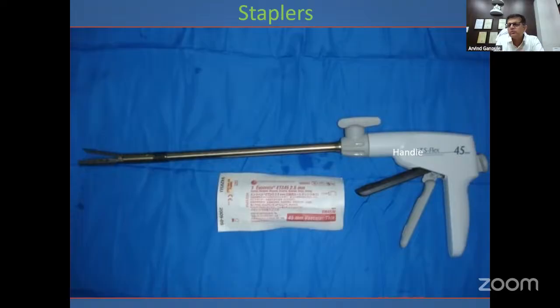So all those horrendous videos that you see, most of the time they are reusing the staplers, or they are not using the proper cartridge. As far as the staplers are concerned, you have got a cartridge, you have got a shaft, and you have got a handle, and the handle has got two knobs. One knob is for application or approximation of the cartridge, and the second is for firing the stapler.